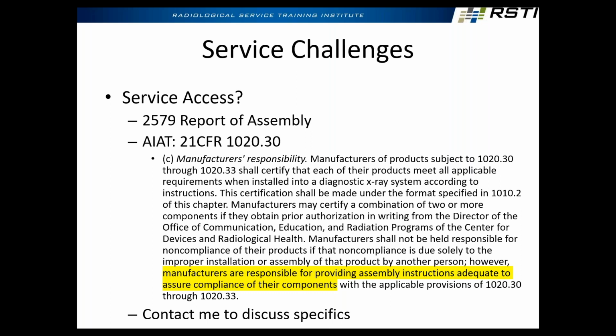And they're called AIAT. So we could talk about AIAT alone for a whole hour, but come see me at the booth if you have any questions. If an OEM tells you you can't service it because you haven't been to their training class or haven't got this key, I can tell you it's BS. There's hoops to jump through, don't get me wrong. They make it hard. That's what we do at RSTI. You need to log in here, get this password, and we hold your hand. Here's how to do it for Siemens. Here's how to do it for GE. Here's how to do it for Philips. And you have to understand those hoops to be able to service these things.